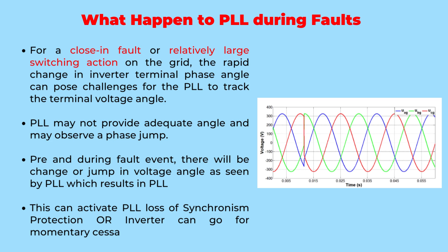In these intense moments, the PLL might encounter a phenomenon known as a phase jump. The sudden shift in the voltage angle, as observed by the PLL, can be quite significant — as if the ground shakes beneath the PLL's feet, making it stumble in its efforts to maintain accurate synchronization. The PLL, perceiving the abrupt change and struggling to adapt quickly, may activate its protective mechanism known as PLL loss of synchronism protection. This safety measure is in place to prevent further complications and to ensure the integrity and stability of the power system.